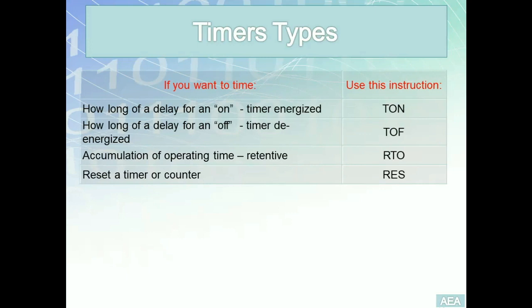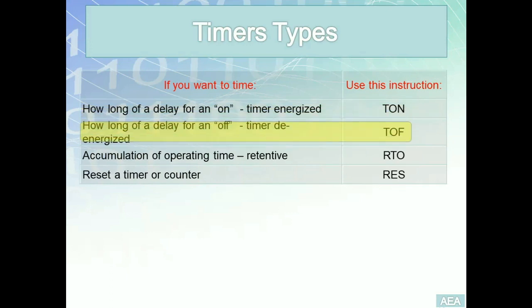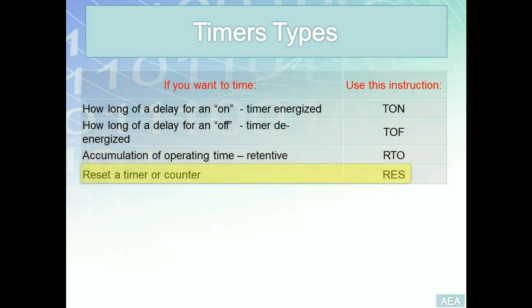Understanding the requirement you come across will enable you to choose the proper timer. If you want a timer to start timing once it's energized, use a timer on delay (TON). In some applications, you may want timing to start after the timer is disabled — that's when you use timer off delay (TOF). If you want retentive timing to accumulate operating time for a device, then RTO is what you need. An important concept is the reusability of timers — if you want to reuse a timer in your program, you must reset it, and one way to do that is using the reset instruction.